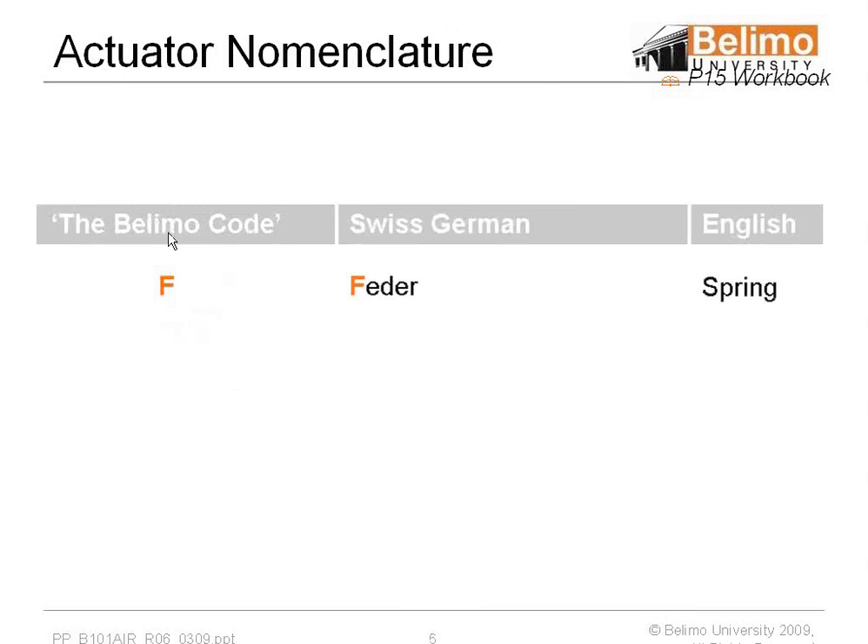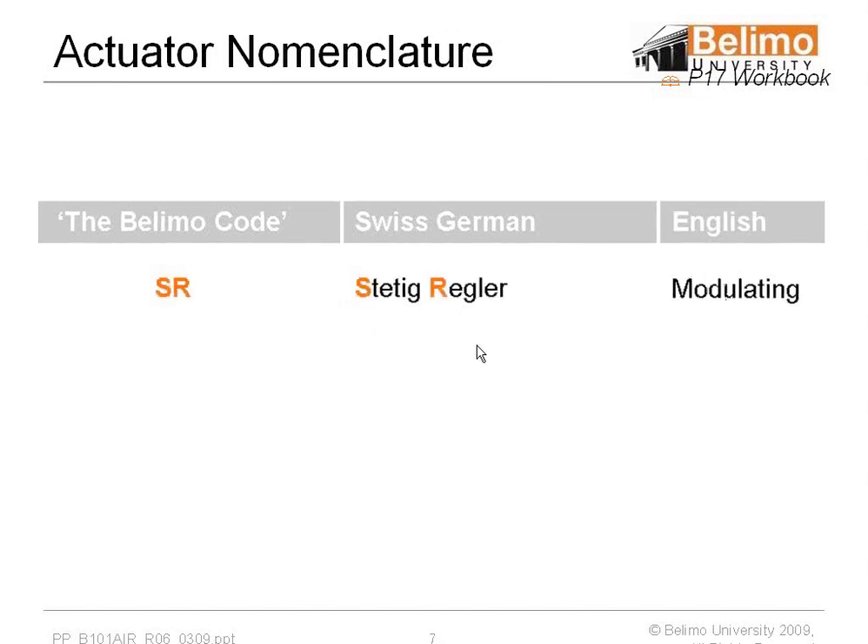On all actuators, the second letter with the designation F is the Swiss German term for Feder, or spring. In SR, which everybody would assume means spring return — and a lot of competitors use SR as a spring return designation — in German it stands for Stetig Regler, or modulating, so that would be a modulating motor. Those two things are pretty important when you're trying to replace a Belimo, because one may think it's spring return, which it could be, but it also could mean it's modulating.